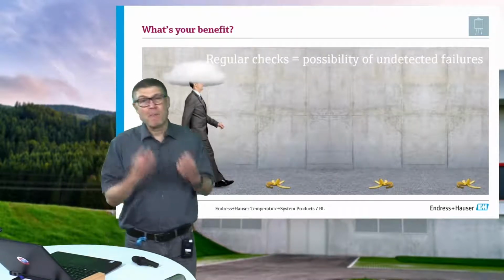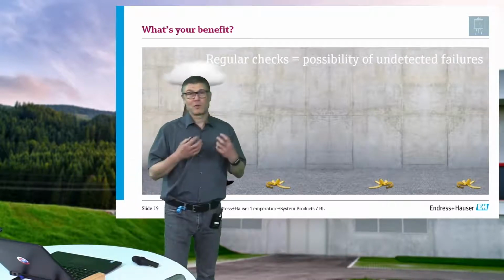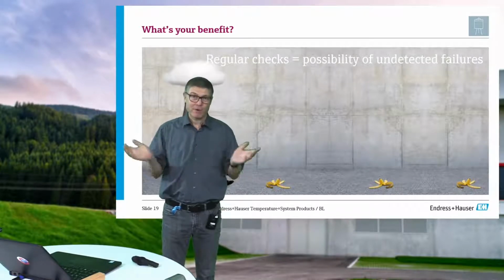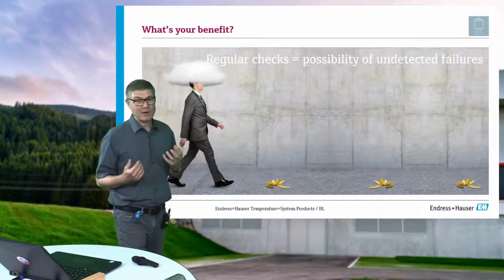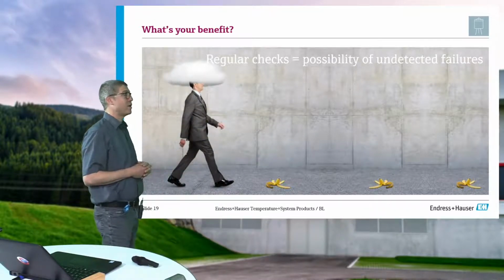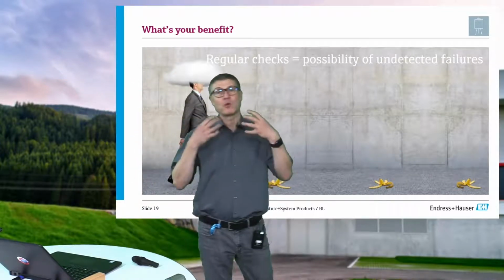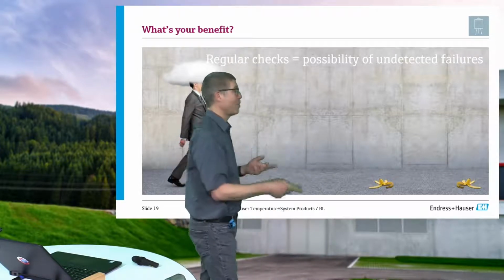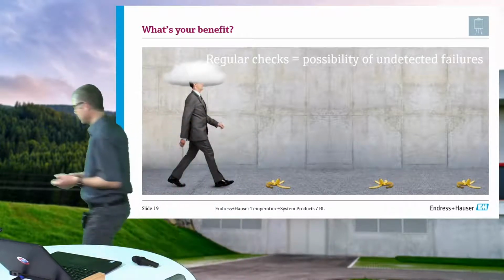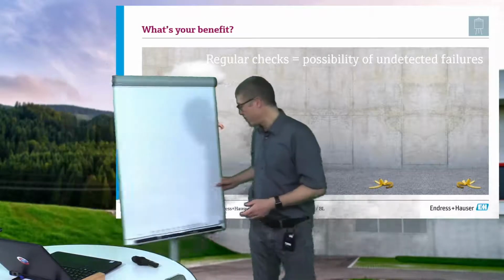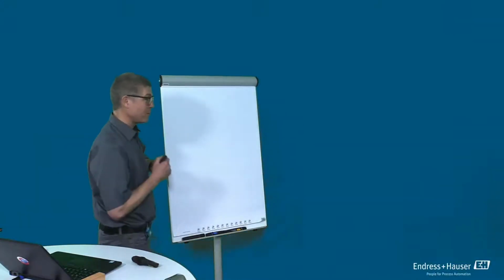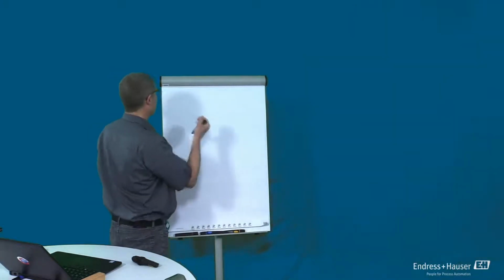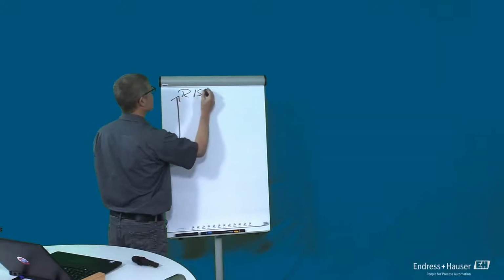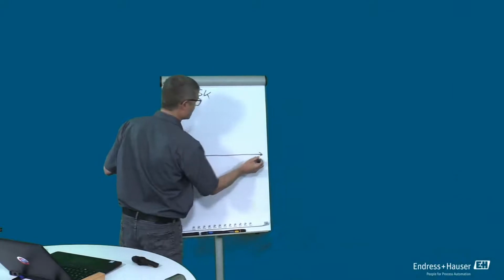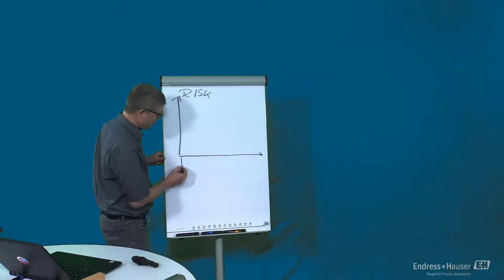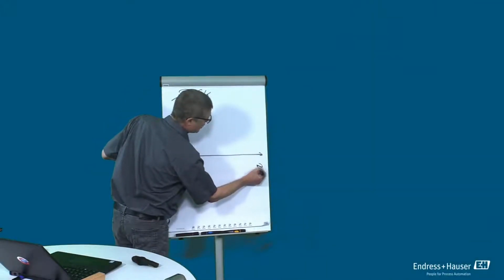So, the main idea behind this is not that you won't do a manual calibration ever again. This is not the idea. We come to this. The general idea is really shown here in a way. You work, you do your calibration, you think everything is fine, and what if something is happening in between? And I like to demonstrate this on the flip chart in a way that if you imagine, so here, that you have the risk and the time. And you do your manual calibration at the time 0. We say we have 24 months here.